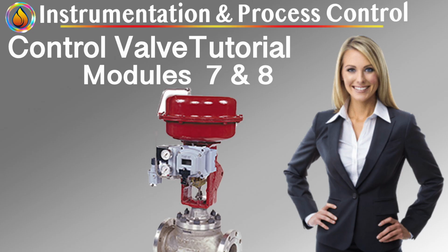Digital smart positioners. Digital positioners fundamentally change how valves behave in loops. Characteristics: microprocessor-based control, continuous position feedback, adaptive control algorithms, embedded diagnostics. Strengths: high resolution and repeatability, adjustable dynamic response, automatic calibration, friction compensation, valve health monitoring. From a control perspective, smart positioners linearize valve behavior, reduce deadband, and stabilize loops that would otherwise be uncontrollable. Their biggest risk is not misuse, but underuse. Deadband, resolution, and response time. These three parameters define whether a valve feels alive or sticky to the controller.